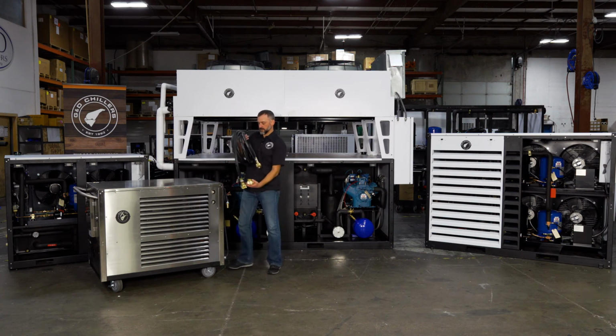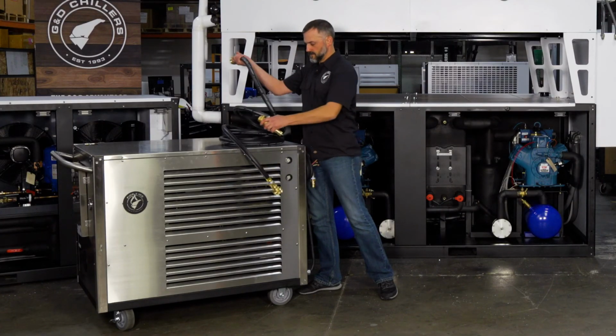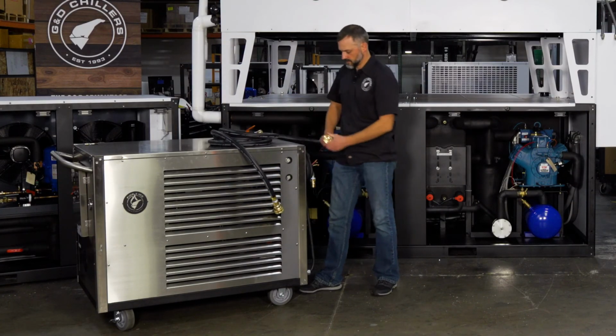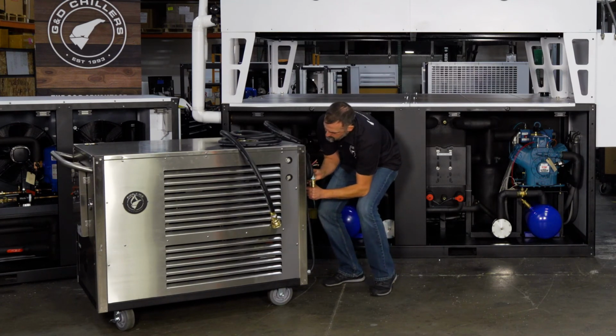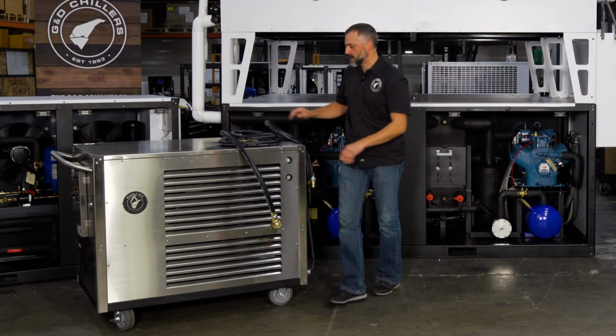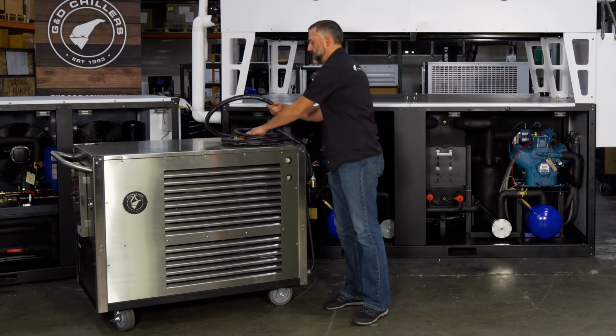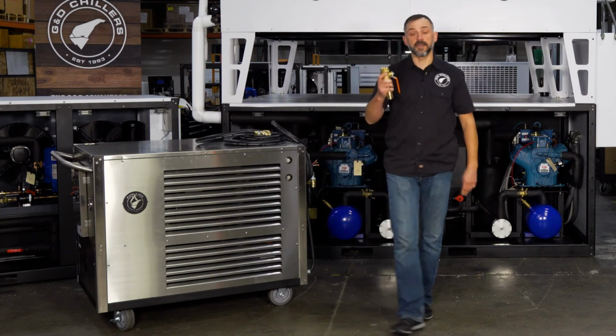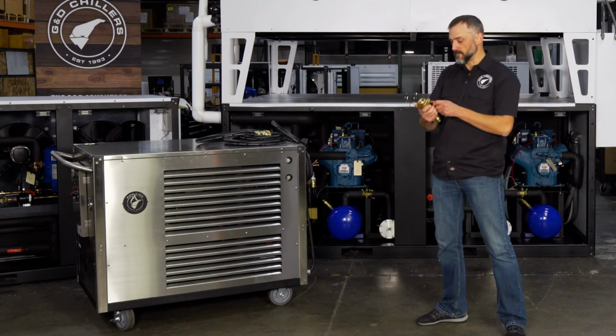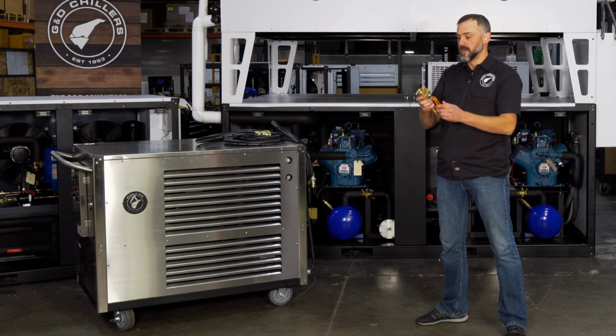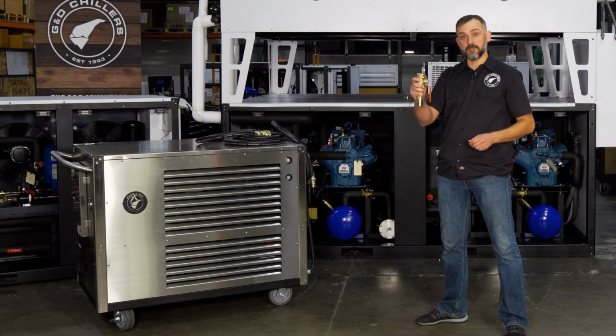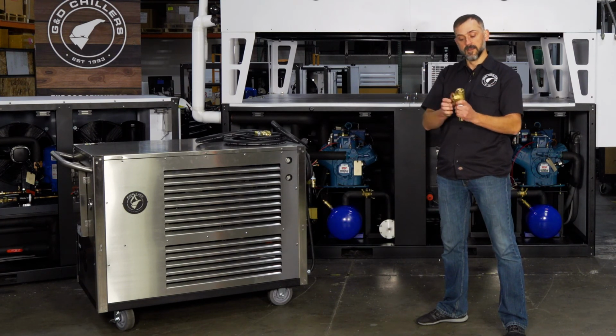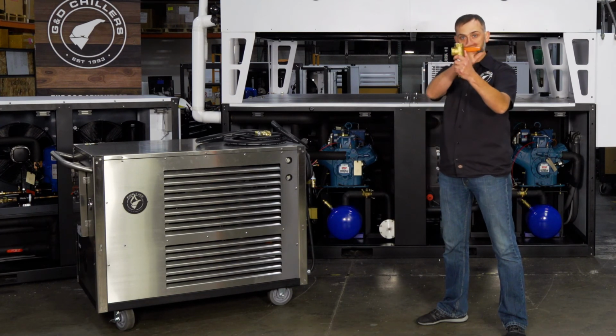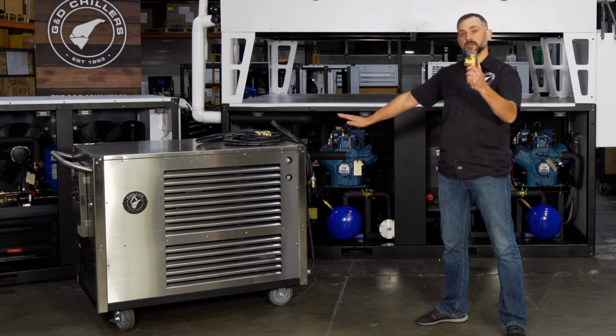You would incorporate the hose onto the chiller like that, and run it to your tank, tying it into this 3-way ball valve, which we can supply ready to go. You'll want one on your supply tank piping and one on your return tank piping, and to isolate from the main line you simply take it from a closed position and open it up here, isolating your tank jacket to the heater or chiller.